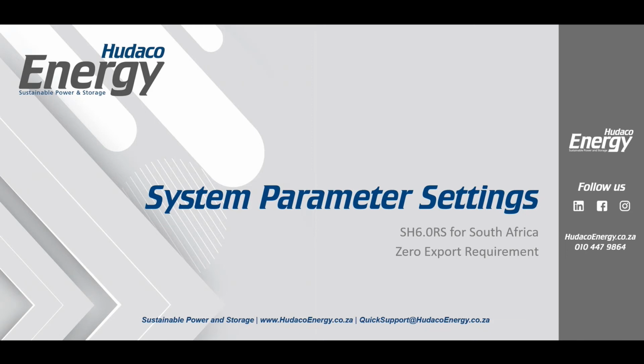Thank you. All right. So I'm going to talk now about parameter settings. These parameter settings that we're going to use are for the 6 kilowatt single phase unit, and they're for the 0 export requirement that we face in most places in South Africa. If you are allowed to export, we'll discuss 1 or 2 settings that you can change very quickly to allow you to export. But this is for 0 export as the primary function for now.